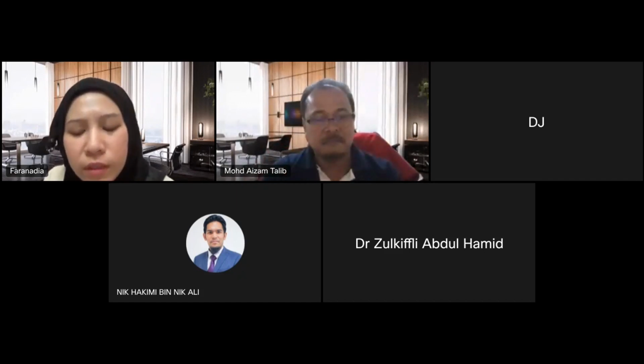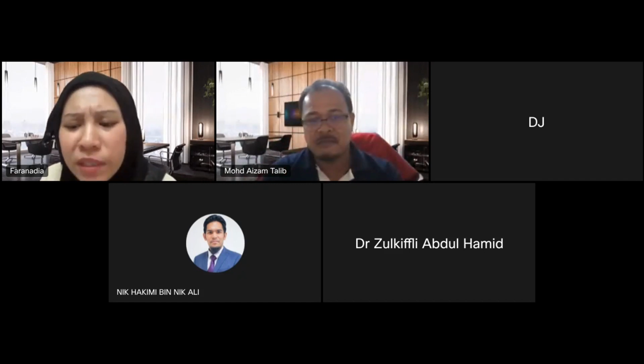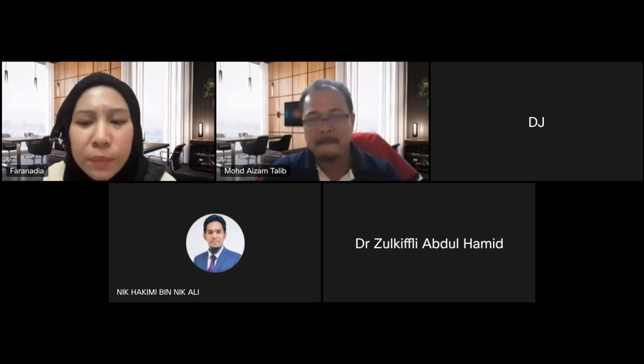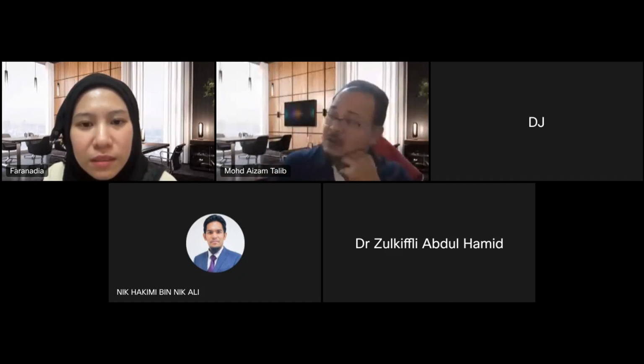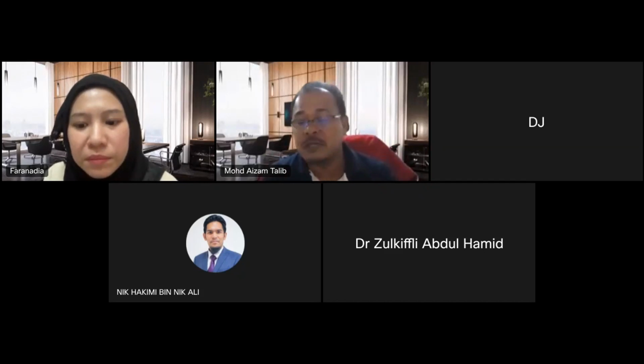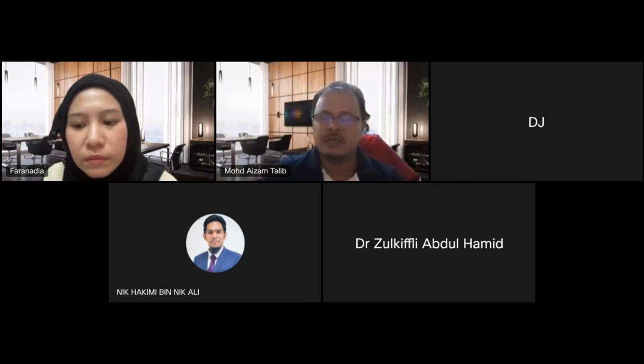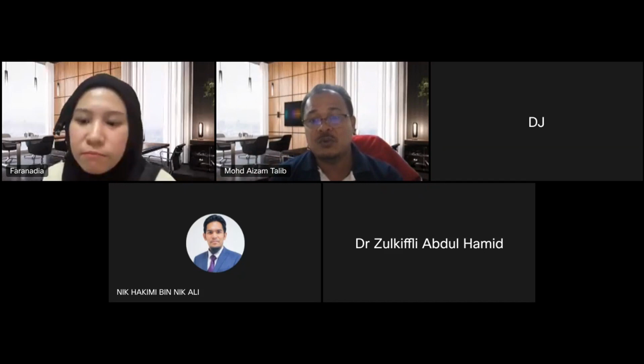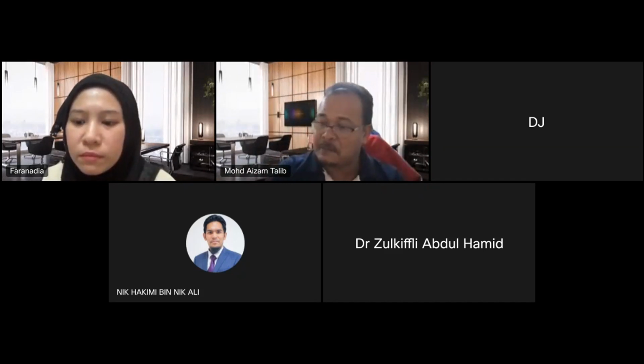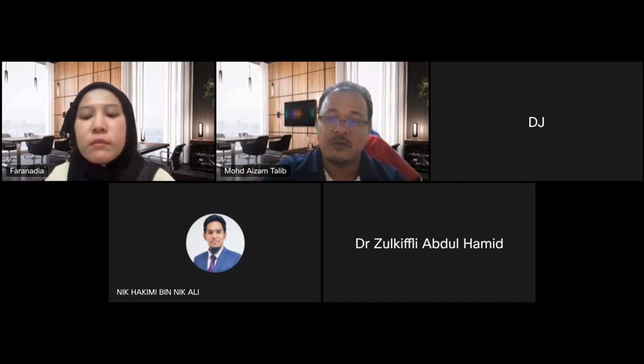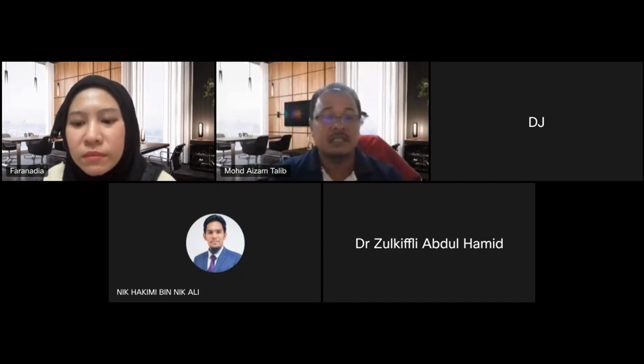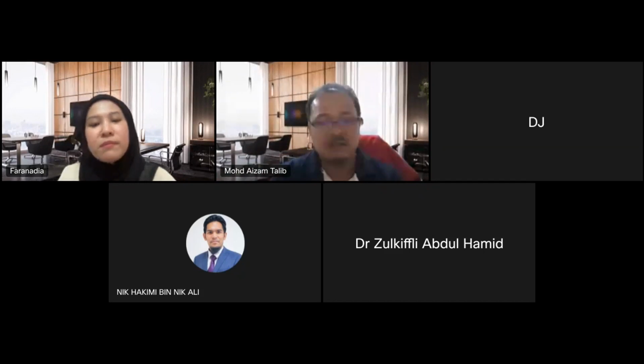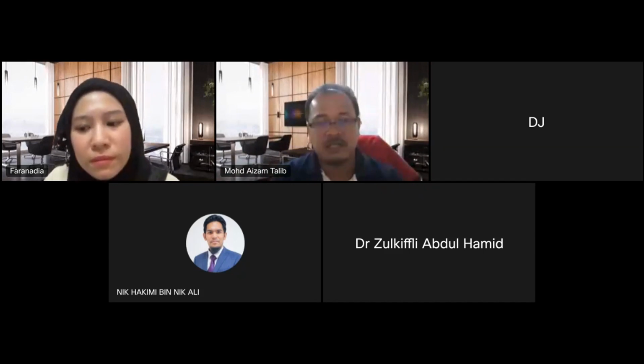Alright. Okay, the next one is more or less the same. From your experience working in TNB, does PD occur frequently? I think the previous answer is that PD occurs, yes. For example, in a transformer, we take the oil sample and send it to the lab, and from the dissolved gas analysis, we are able to see the presence of overheating, partial discharge, and arcing. I think this is a common phenomenon or common issue that we face in our electrical equipment.